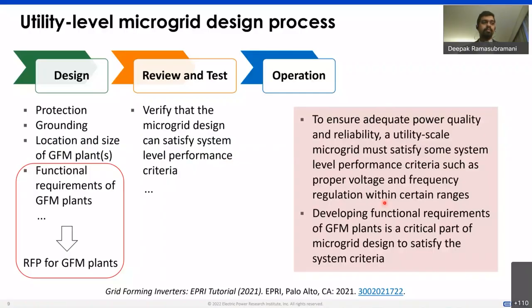If you look at a typical utility level microgrid design process today, and here utility level microgrid means a microgrid that involves at least part of the medium voltage feeder and different generation resources and customers connected at different locations, at the end of the very first step, which is the design phase, there will be requests for proposals, RFPs, issued for grid forming plants, within which the performance requirement for the grid forming plant and the inverter will be developed. The goal with those requirements is to ensure adequate power quality and reliability in the utility scale microgrid, and developing functional requirements of the grid forming plant is a key part of achieving that. Next slide, Deepak.